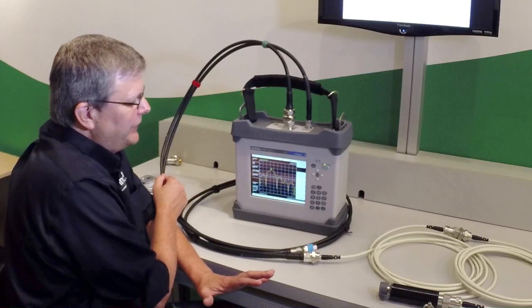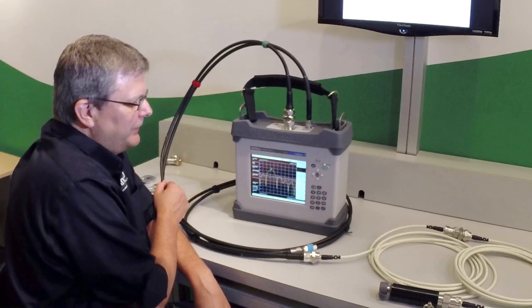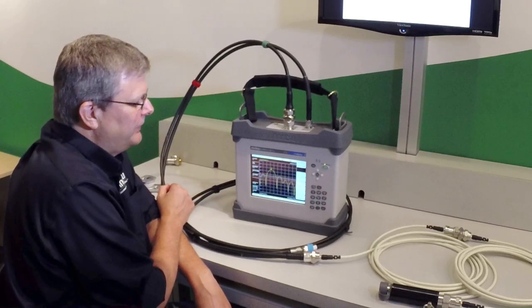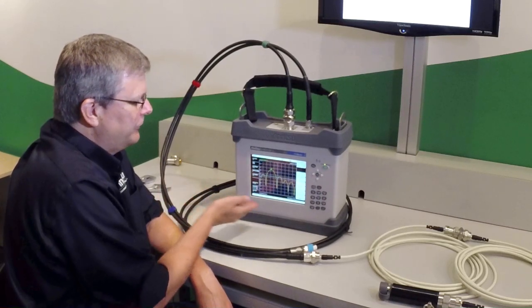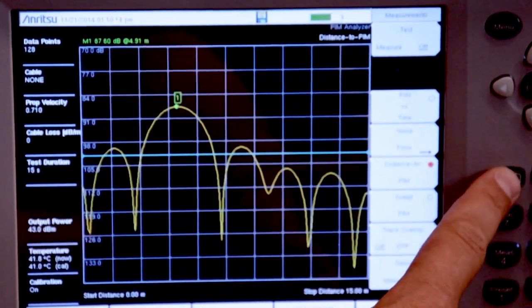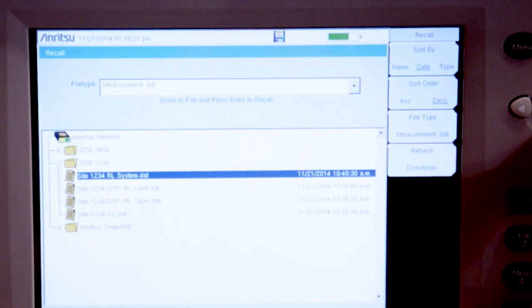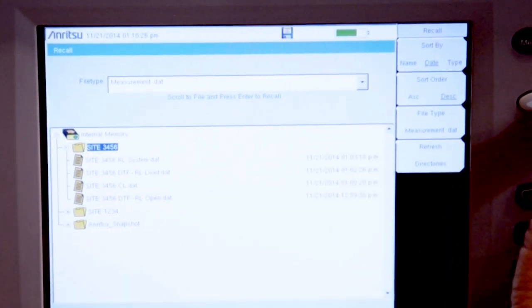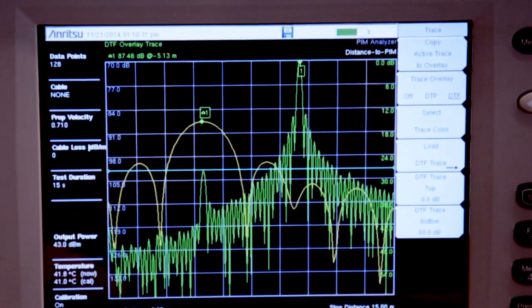A new capability of the B series PIM master is that because we did our cable antenna analyzer measurements on the same instrument, we can use those DTF measurements we did in cable and antenna analyzer mode to help us gain more information about the location of this PIM problem. So what I'm going to do is hit shift trace, load a distance to fault trace, and we're going to go into the site directory that we were looking at. The first one I'm going to load is the distance to fault measurement where we had the open circuit at the end.